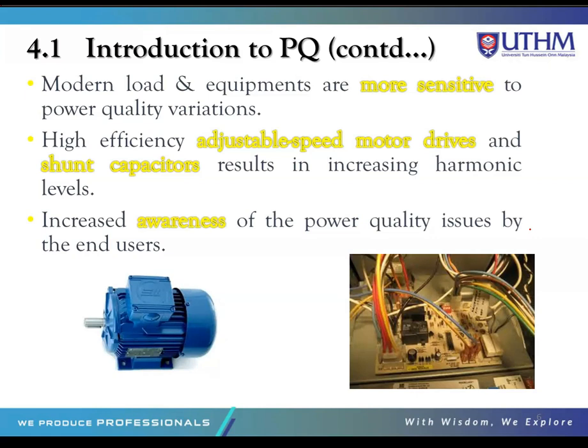Modern loads and equipment are more sensitive to power quality variations. High efficiency adjustable speed motor drives and shunt capacitors result in increasing harmonic levels. In an electrical power system, a harmonic is a voltage or current at a multiple of the fundamental frequency, produced by the action of nonlinear loads such as rectifiers, discharge lighting, or saturated magnetic devices. Increase in harmonics results in increased heating in equipment and conductors.